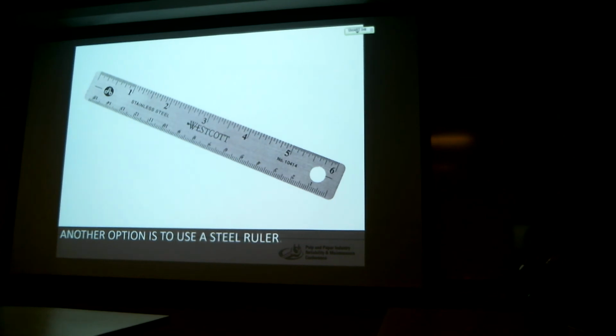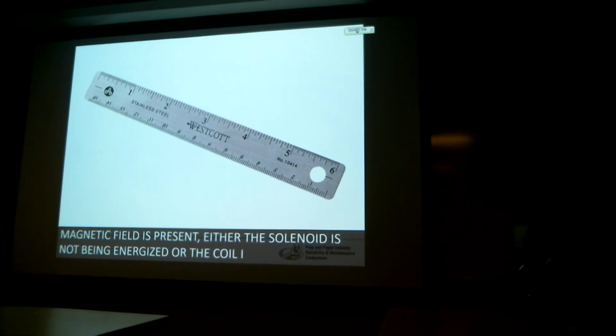Another option is to use a steel ruler. Whenever a solenoid is energized, if it's functioning properly, a magnetic field will be generated. The ruler will be attracted to the solenoid. If no magnetic field is present, either the solenoid is not being energized or the coil is burned out.